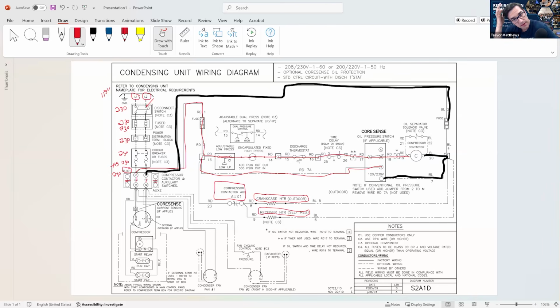Because if you came in here, the way I mentioned that Rusty likes to do it, he would start and he would just have it on L2 and he would just start right at 3, break it up right in the middle of the circuit. And all of a sudden, if he's got 120 volts there, he knows something upstream is open, right? Because we're not getting that voltage there. So there's something up here that would be open.